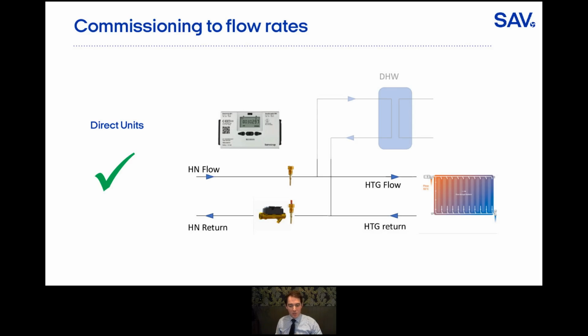And this is what we can do with a direct unit. On a direct unit, you have a direct connection from the heat network into the space heating circuit. Via the metering and billing regs, you have an energy meter that you have to install there, and that energy meter can measure flow and can measure delta T. So you've got a tool already installed that you have to have there to see your flow rate and your temperatures.